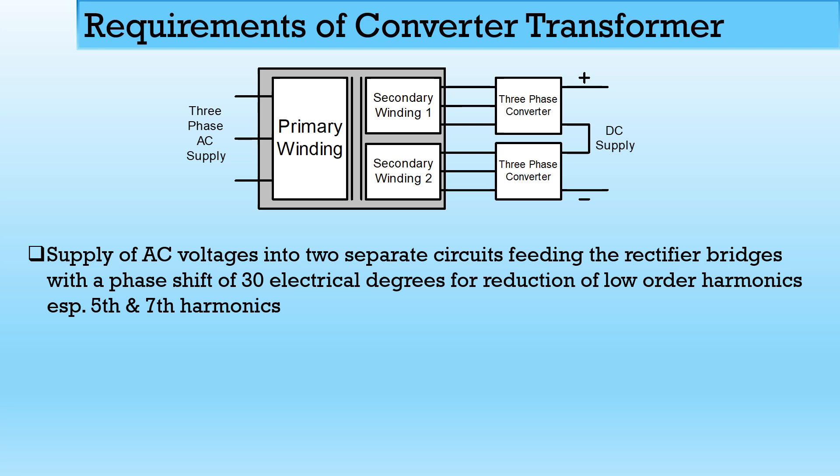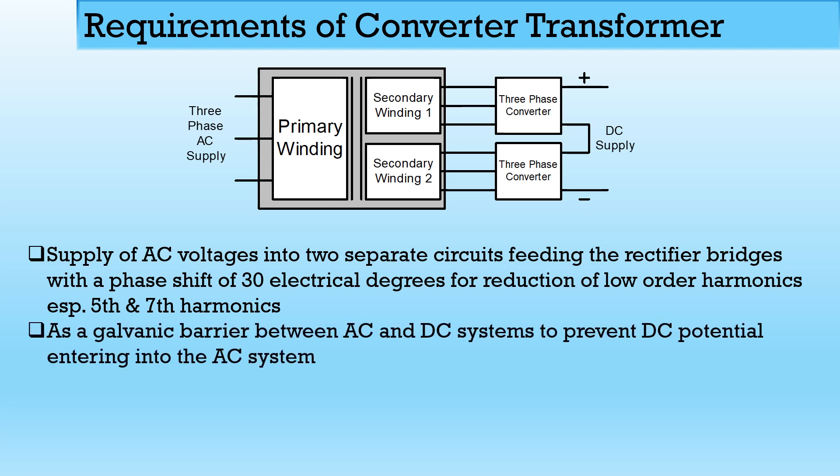The first winding supplies 0-degree phase shift and the second winding supplies 30-degree phase shift. Another requirement is to act as a galvanic barrier between the AC and DC system to prevent DC potential from entering into the AC system. If we connect AC directly to the converter, it will not provide galvanic isolation, so noise signals and harmonics would be easily introduced into the AC supply. The converter transformer keeps the isolation between them.